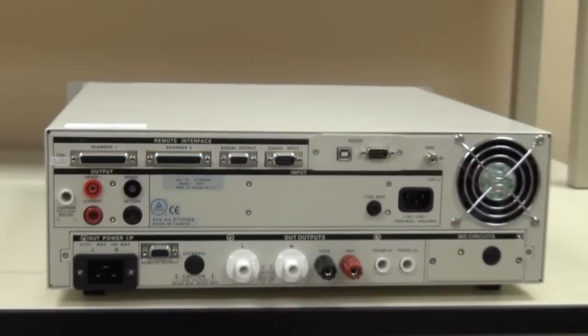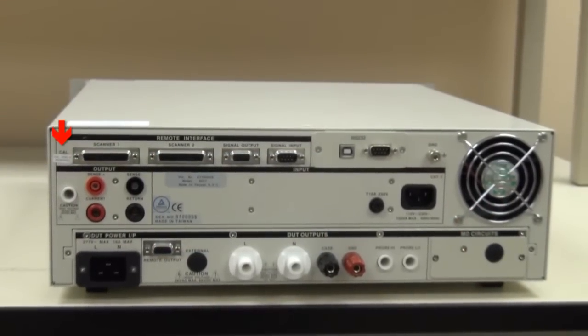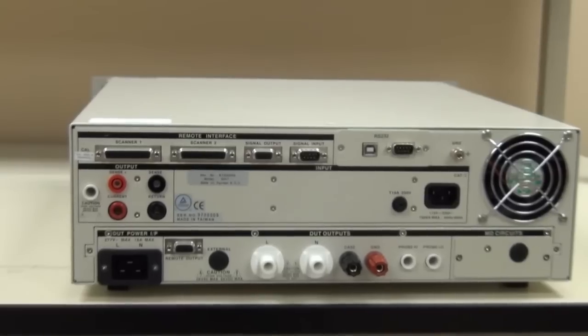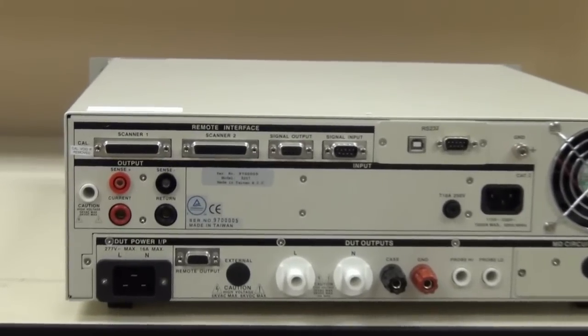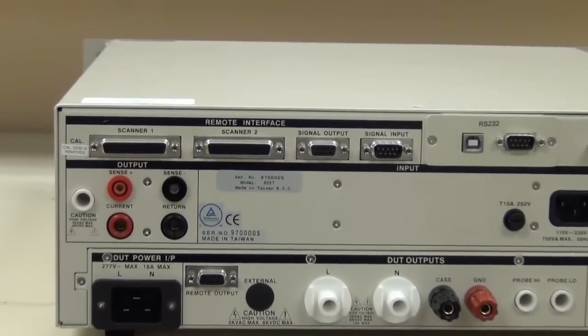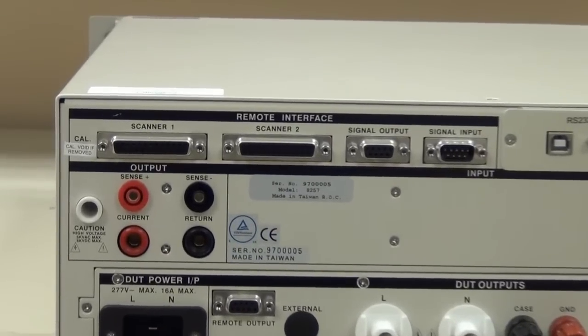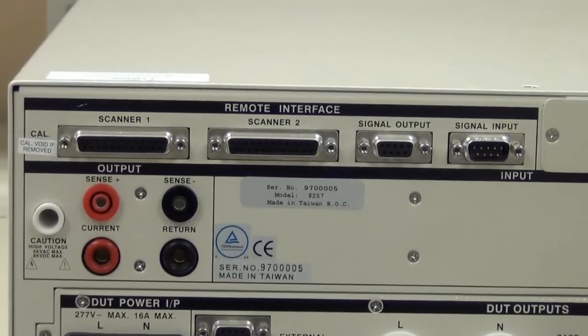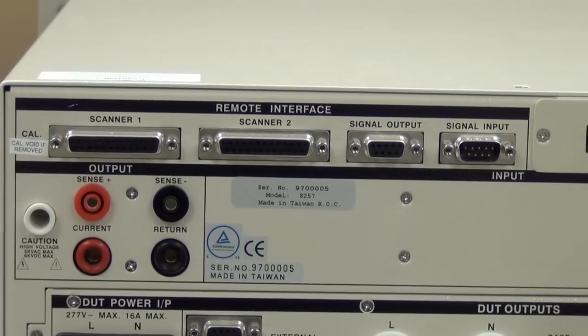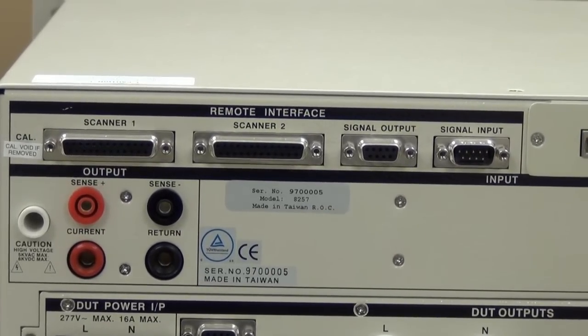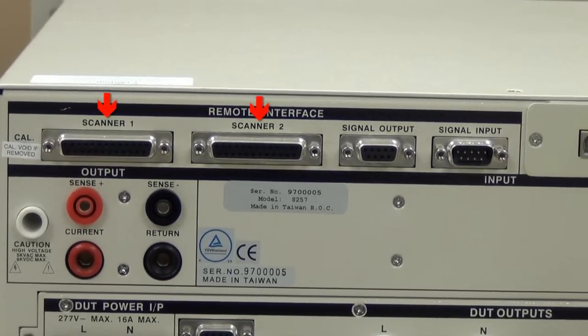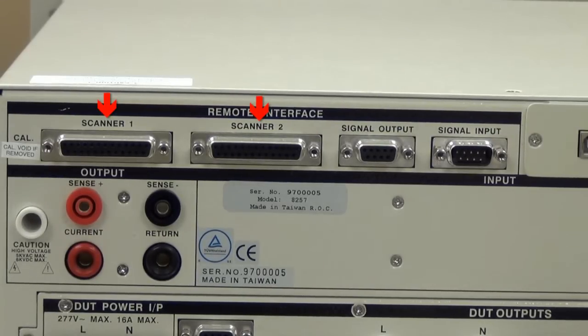Next are the rear panel controls. The calibration button is used to put the instrument into calibration mode. To put the unit into calibration mode, push and hold this button while simultaneously turning on the power switch. The scanner connector is used for connection to an Associated Research Inc. SC6540 slave scanner. The Omnia II comes standard with 2 scanner connectors to allow the Omnia to control up to 2 SC6540, 8 high voltage, and 8 ground bond channel scanners.